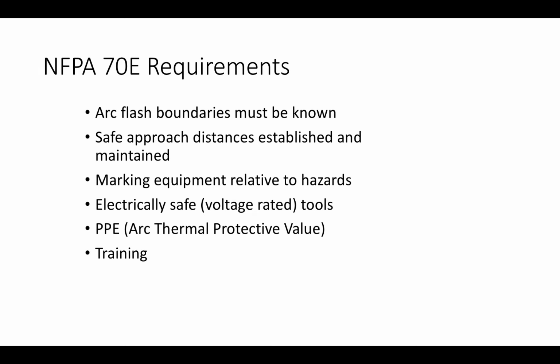NFPA 70E is the standard having to do with arc flash. The requirements are that arc flash boundaries must be known and established. Safe approach distances must be established and maintained. Equipment must be marked relative to hazards. Electrically safe tools must be used. And you must wear personal protective equipment that has an arc thermal protection value appropriate for the job, and you must be trained.